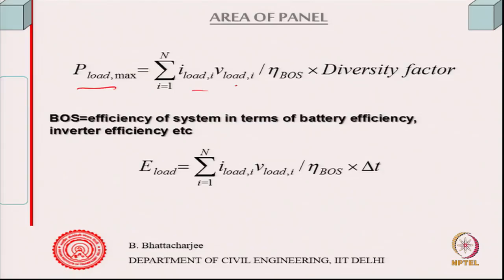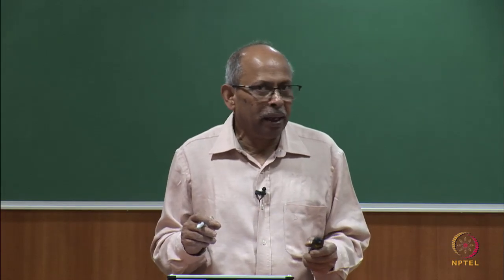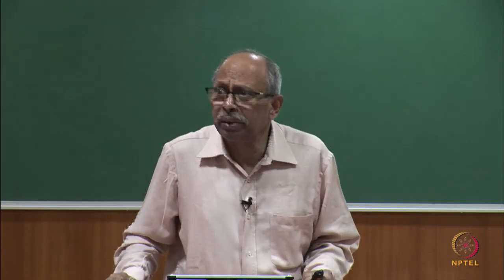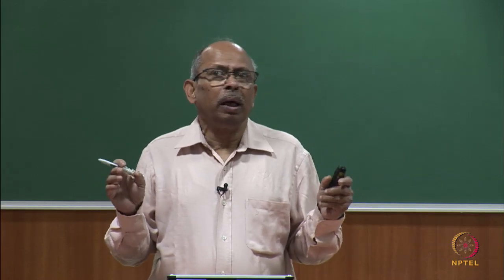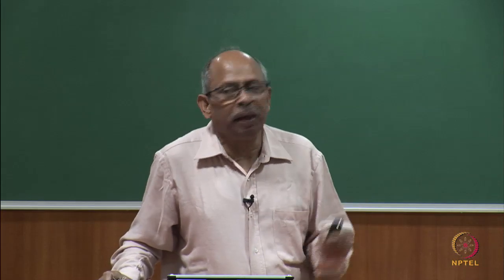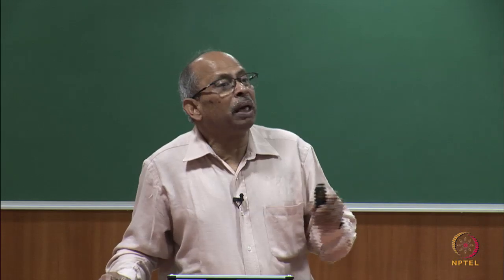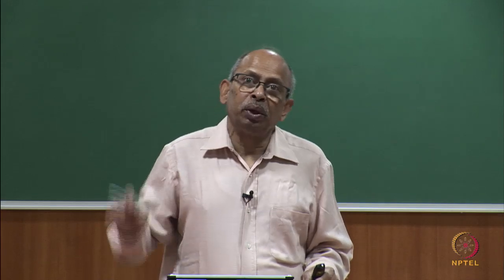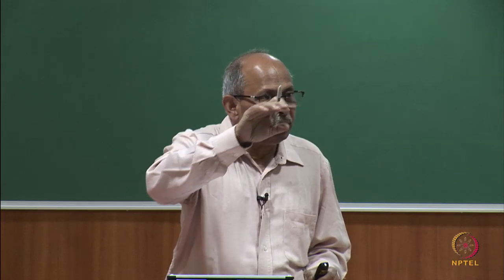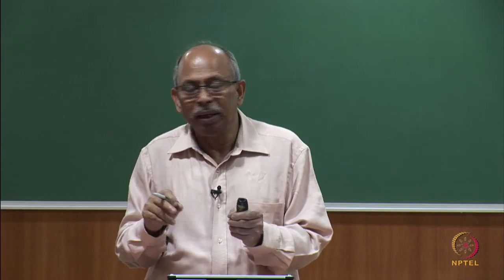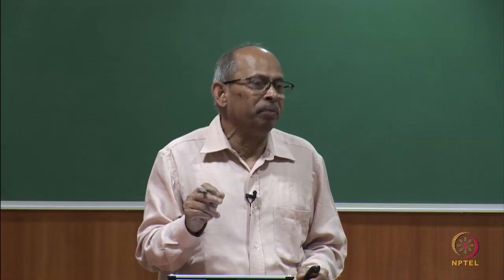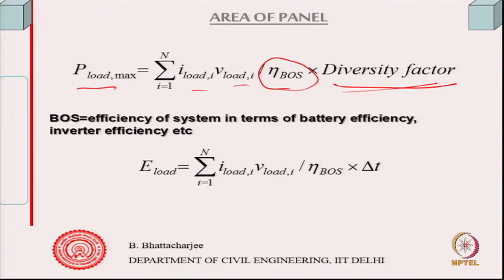P_load maximum would be I_load times V_load divided by efficiency, multiplied by a diversity factor. The diversity factor accounts for the fact that all loads will not be at their maximum peak simultaneously. For example, this room is connected to a number of lamps each drawing 5 amperes — the probability that all lamps in all rooms are on simultaneously is less than 100%. So the cable capacity is 5 × n × diversity factor, not simply 5 × n.